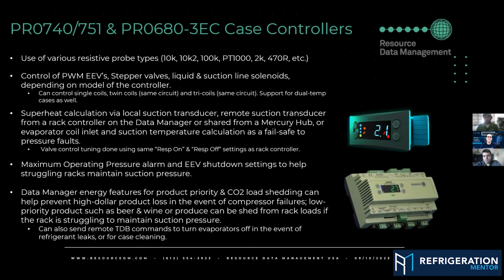But if they have their own local pressure transducer and they see that the suction pressure is getting, maybe we're 10, 15 degrees above saturated for our normal suction pressure, you can tell that valve to go to 50%, 20%. You could tell it to close entirely. And it's a way that the case controller can help the rack, kind of try to recover its suction pressure.